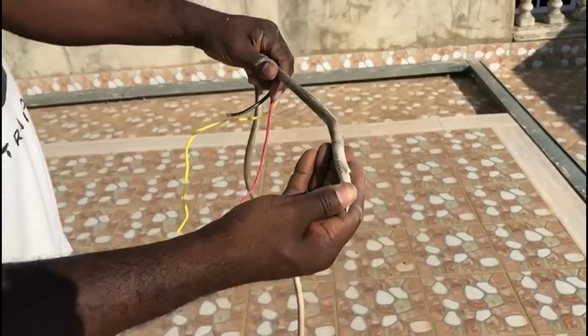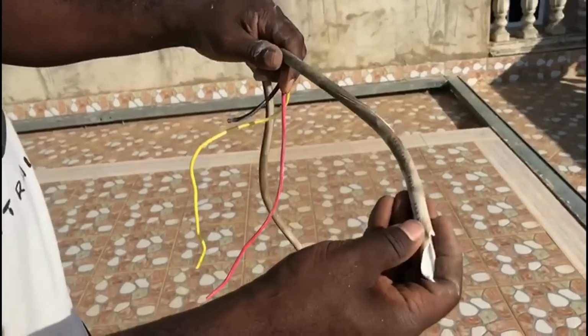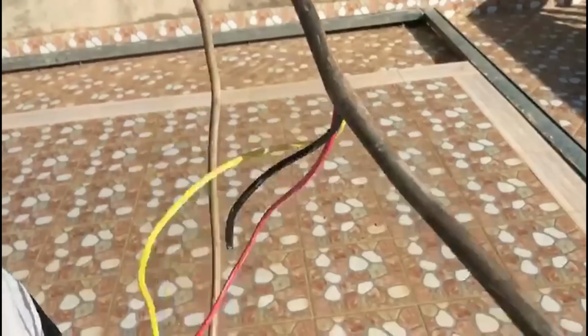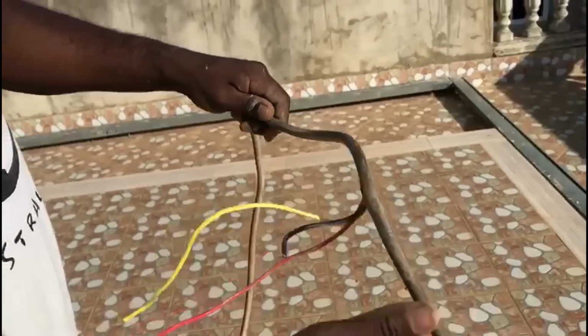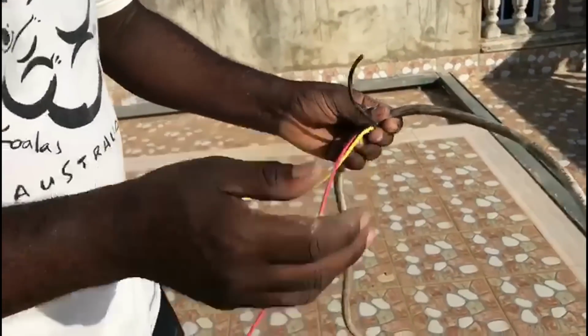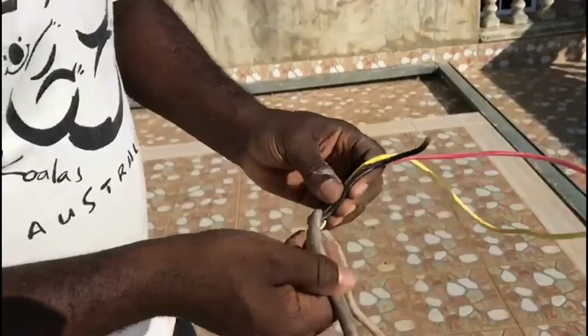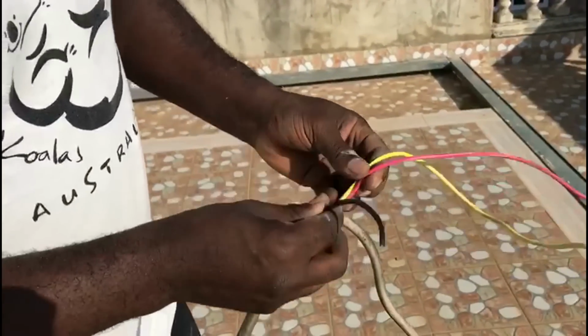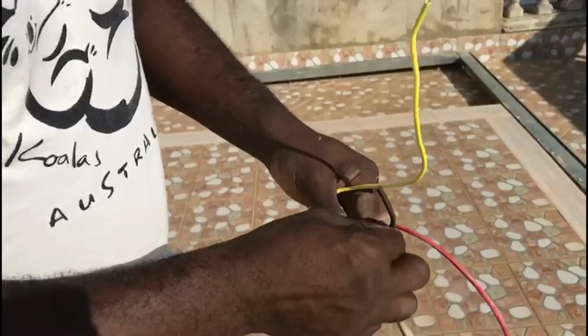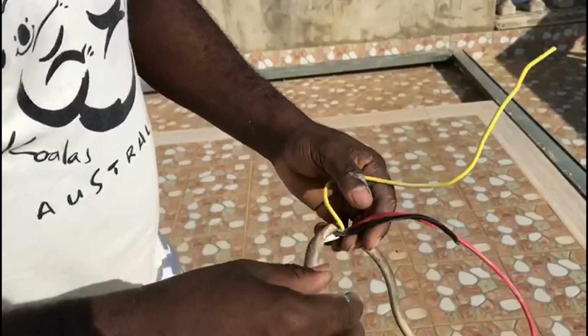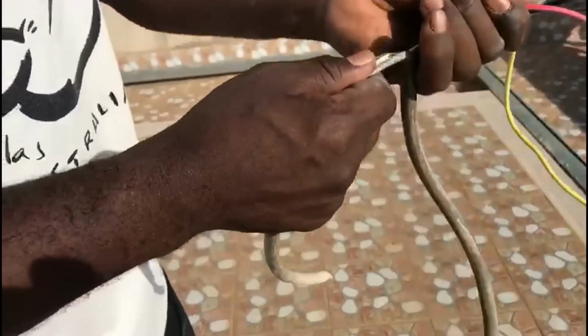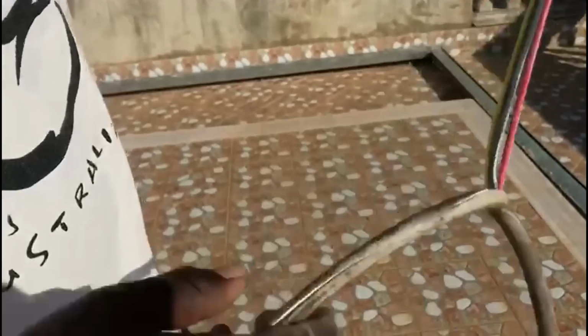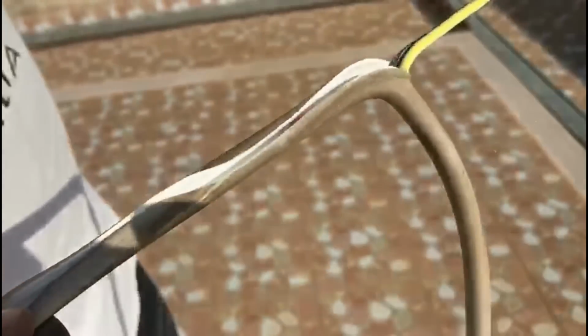So this is a 2.5 mil cable. It looks like a good cable, made in China. We've had it installed for many years, but all of a sudden my pump stopped working. As I told you, I checked and changed the fuses, everything worked, no problems with the power supply, but it turned out the cable had burnt. When I strip it out, you can see, if you look closely, some ash coming out, and the cable just rips apart very easily.